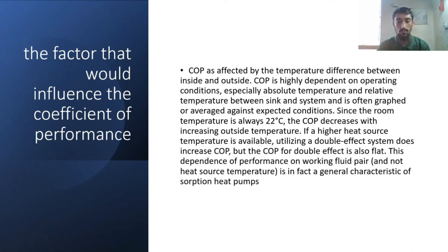If a higher heat source temperature is available, utilizing a double effect system does increase COP. But the COP for double effect is also flat. This dependence of performance is on the working fluid pair and not on the heat source temperature. It is in fact a general characteristic of sorption heat pumps.